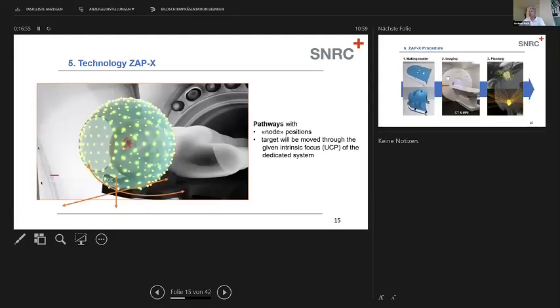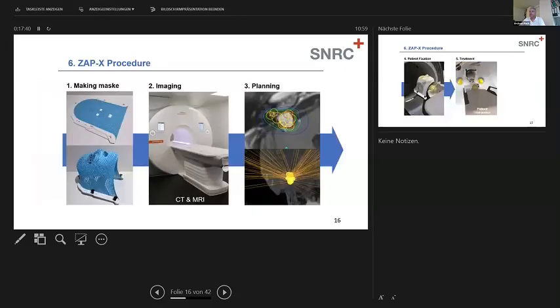So this would be the situation if you look at the inside of the machine. All yellow points are so-called node positions, which can be addressed by the LINAC, and the LINAC will point to the unit center point. That means at a certain position, all these nodes are addressed by the LINAC, the so-called step and shoot procedure. After this has taken place, you have irradiated one part of the lesion. Then the lesion will be moved back and forth, right and left, up and down, and then a different part of the lesion is in the focus. So the target will be moved through the given intrinsic focus. So this is the procedure.